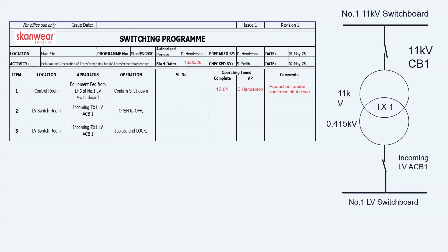Item one: I'm going to go to the control room and make sure the equipment fed off that switchboard has been shut down, because I don't want to start opening circuit breakers or switches under load. So I need to try to reduce that load down as much as I reasonably can before starting my isolations. I've asked the control room to shut this down, and got confirmation at 12:01 that it's been done—the production leader confirmed all that equipment has been shut down. I can verify that by looking at the ammeter or by the SCADA or DCS system to see there's no load on that network.